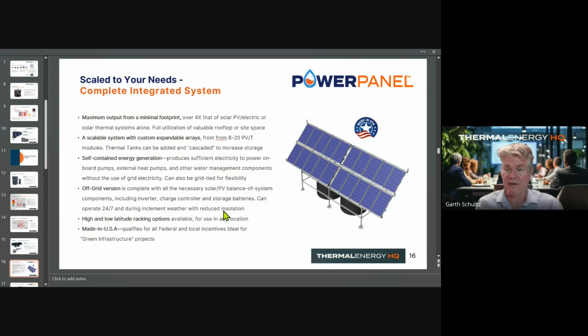The standard building block is 20 modules, as pictured, and we can build out that capacity based on your needs and use. Underneath that particular array, we have 2,700 liters, about 700 gallons, of storage. If you have processes where the PVT energy is used up instantly in your building's process, the thermal storage element becomes smaller. But if you have a process like an industrial laundry with no use on weekends since no one is cycling it out, you'd want to maximize storage so that when they come back Monday, the sun that came out Saturday and Sunday is put to use then.